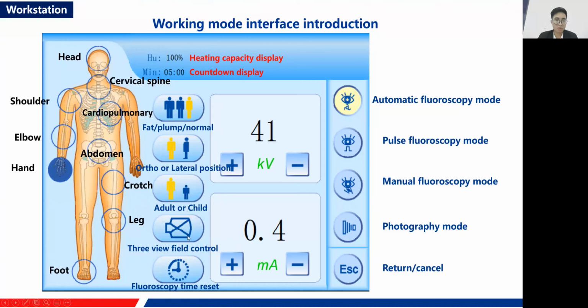So this is the three view field control button. Okay. And this one, the reset, is for the fluoroscopy time reset. It works with this one, minute. There's a countdown, a five minute countdown from 5 to 0. Once it reaches 0, you cannot use the fluoroscopy anymore, and you need to press this reset button, and it will start from 5 again, right? So here 100% is our heating capacity display. This also goes from 100% all the way down to 0. And once it reaches 0, that means the tube is overheated and you need to cool it down, so you can continue to do the fluoroscopy or the photography, right?